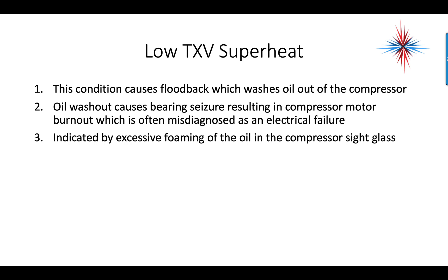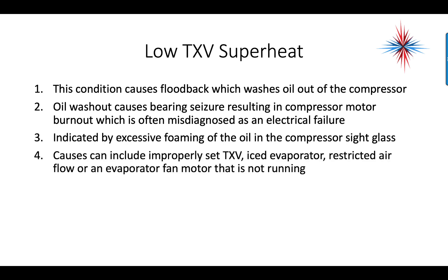If you're looking at a compressor that has a sight glass and you see foaming of oil — like a milky foam — you're getting liquid refrigerant back into that compressor. Causes can include an improperly set TXV, iced evaporator, restricted airflow, or an evaporator fan motor that is not running.